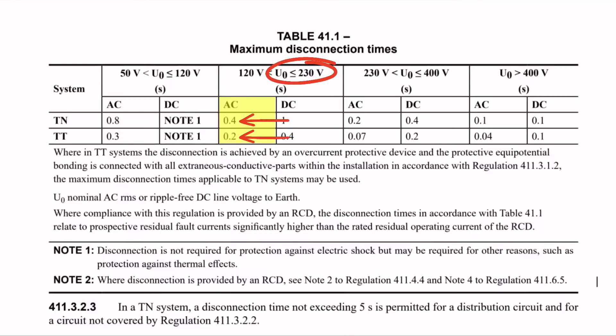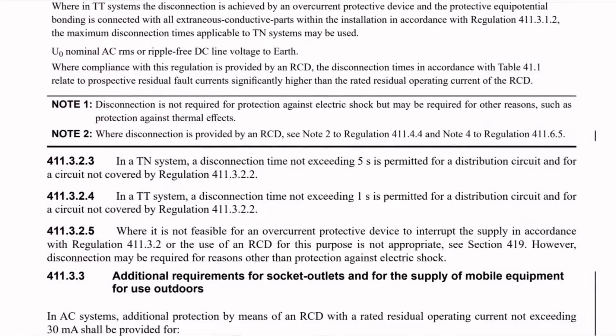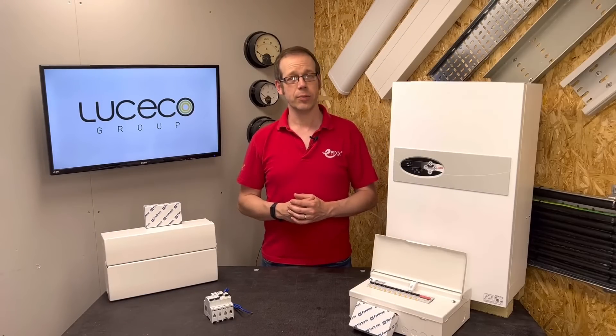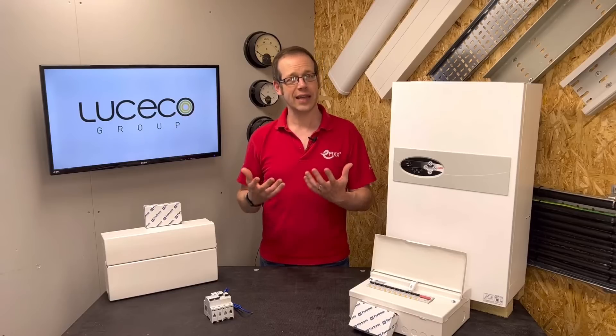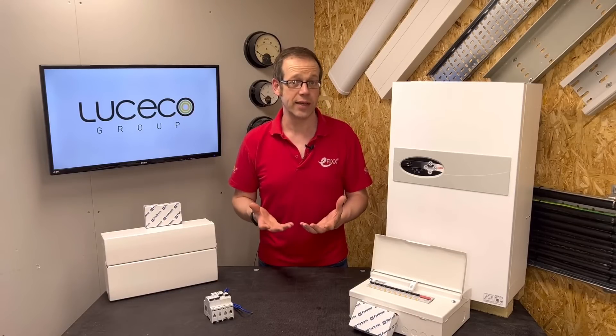Our circuit — supplying a 9 kW fusion comet electric boiler — has a rated current of 50 amps and doesn't fall within regulation 411.3.2.2. Regulation 411.3.2.3 states that in a TN system a disconnection time not exceeding 5 seconds is permitted for a distribution circuit and for a circuit not covered by 411.3.2.2. So our circuit can disconnect within 5 seconds. However, in practice it will actually disconnect within 0.4 seconds anyway.